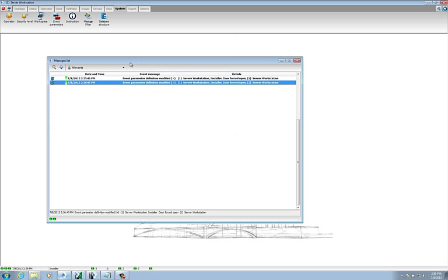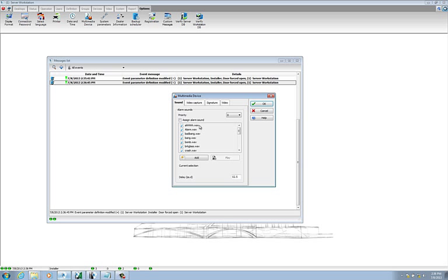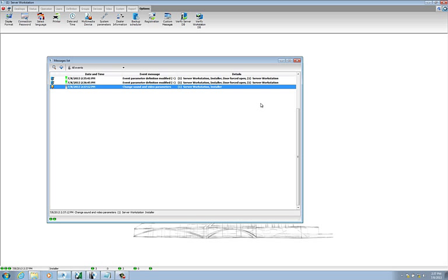The next thing, we're going to go to option and then multimedia device. On the multimedia device, we select our priority, which was 2, and then which sound we want to assign to it. Check the box, assign the alarm sound, and select the specific wave that you want. For now, we're going to select the alarm, and then we can do a test. Okay, and then we click OK.